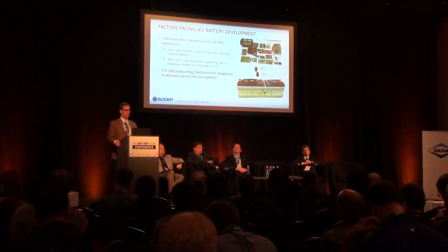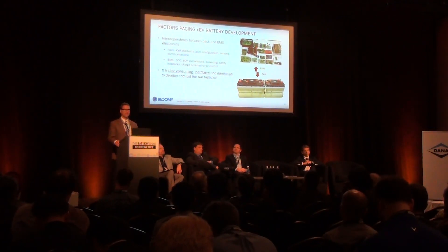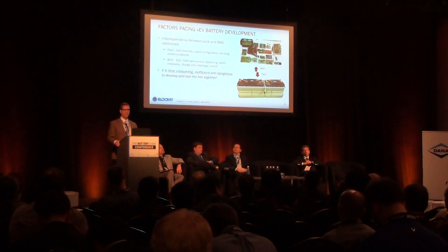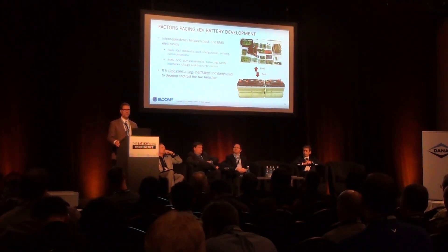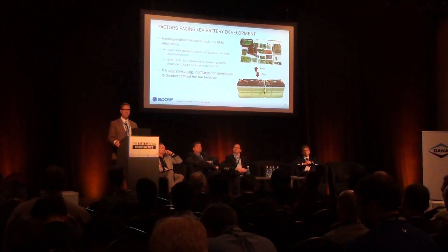In particular, you're wasting a lot of time if you're waiting for a pack prototype to be available. Once the pack prototype is available, how much testing can you really accomplish with your BMS? To test all of the functions that the BMS is designed for, you would have to have thousands of packs exhibiting all kinds of different behaviors and faults. Moreover, testing with a pack as the stimulus is not a repeatable test because packs degrade with every charge and discharge cycle. So in order to have repeatable BMS testing, you need to simulate the pack using an electronic alternative.